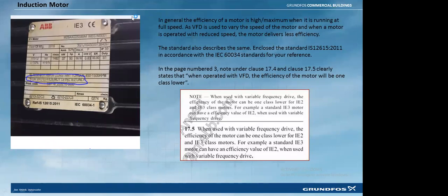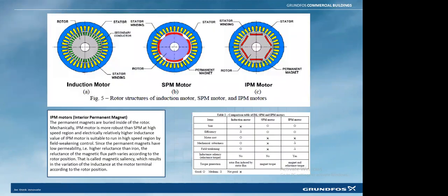So when we come up with a higher efficiency motor, whether IE3, IE4 or IE5, what is the design approach to eliminate this particular issue? Now when we come to IE5, in IE5 motors we use a permanent magnet construction. In permanent magnet construction there are two types: one is the surface mounted permanent magnet, and the other is the interior permanent magnet. In our Grundfos IE5 motor, we use interior permanent magnet motors.